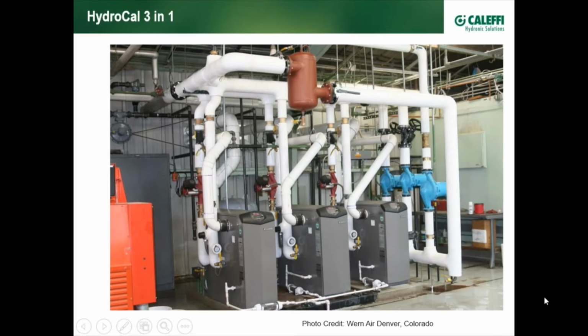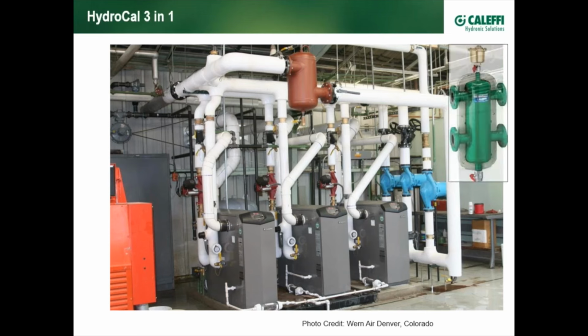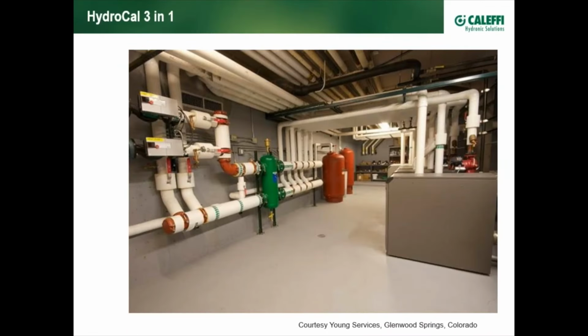This is a job that could have benefited from a HydroCal. Before this excellent contractor knew of the HydroCal, or even Caleffi for that matter, they constructed this system and they have let us use the photo for illustration purposes. If they had considered using a HydroCal, they could have eliminated the closely spaced T's in the crossover connector, considered eliminating the three Y strainers going down to each of the condensing boilers, and eliminated the air separator. In doing so, simplifying the piping quite a bit, such as this job from Colorado as well.